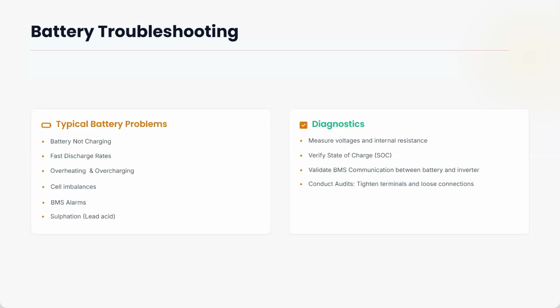So then BMS alarms could come up when overload occurs. Maybe the battery is overloaded, because it's a sensitive and intelligent battery. We're not talking of lead acid batteries now. It's lithium batteries that have a BMS. So when they see shock, like overcurrent, over voltage, under voltage, they go to alarm mode to protect themselves. So it's just a way to protect the battery so that it doesn't get damaged. That's why I said they are intelligent. So you may not know what's going on, but you see the result that, oh, the system is shut down. What caused it? It could be alarms showing on the indication or on the battery. So you take care of that, and once it's resolved, then the system comes up.